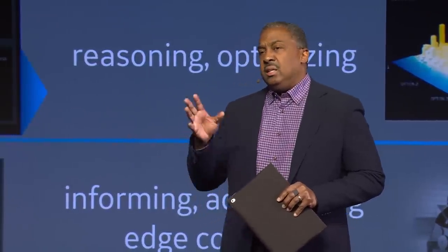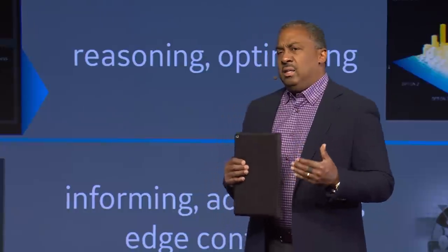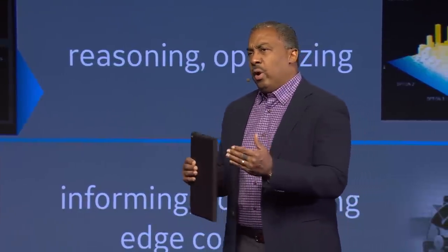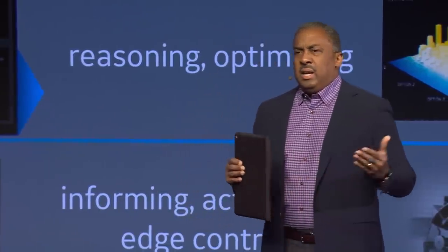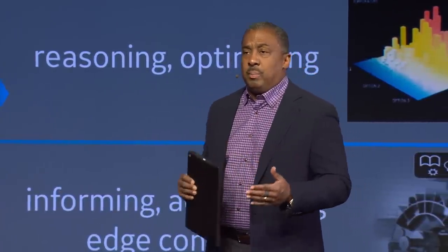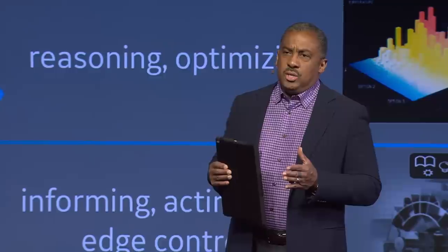In the seeing stage — relating this to what you saw previously — it's gathering data of its situation to give you a warning or a prediction. This data is both operational and environmental: steam temperatures, bowl temperatures, rotor speeds. It takes that data in and uses a living model — a hybrid model of physical and digital capabilities — combining metal fatigue, metal creep, Bayesian learning, and other machine learning techniques to create a cumulative damage understanding of what's happening on that rotor.